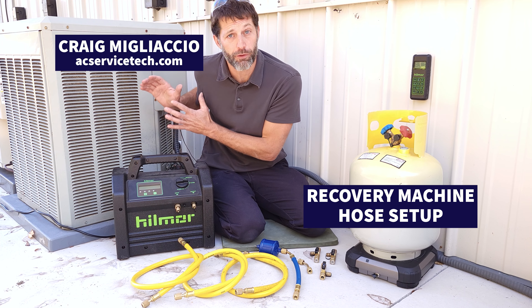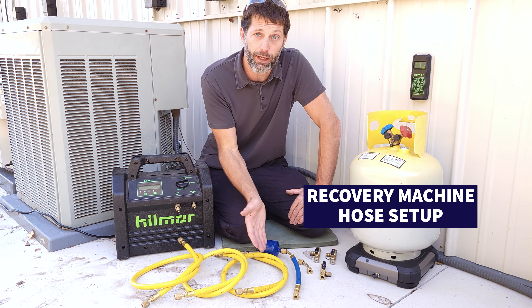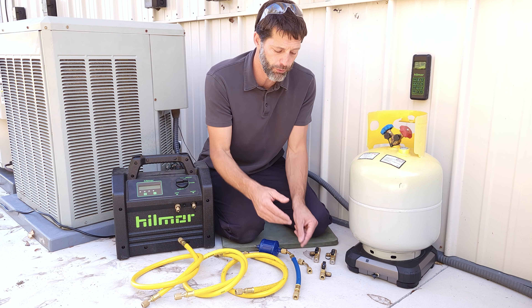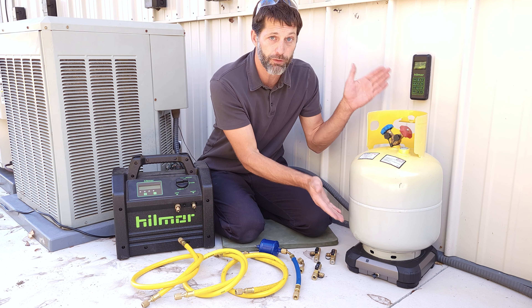Today we're recovering the full refrigerant charge from this air conditioning system using our hilmor recovery machine, three three-eighths by quarter inch hoses, a filter dryer, a short piece of hose or an adapter, three valve core removal tools, and our digital wireless scale.